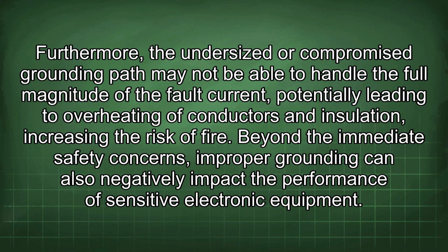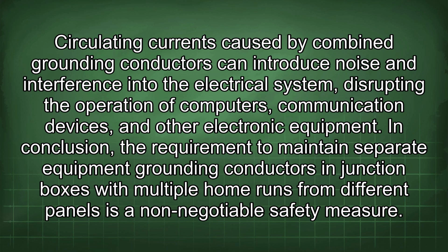Beyond the immediate safety concerns, improper grounding can also negatively impact the performance of sensitive electronic equipment. Circulating currents caused by combined grounding conductors can introduce noise and interference into the electrical system, disrupting the operation of computers, communication devices, and other electronic equipment.